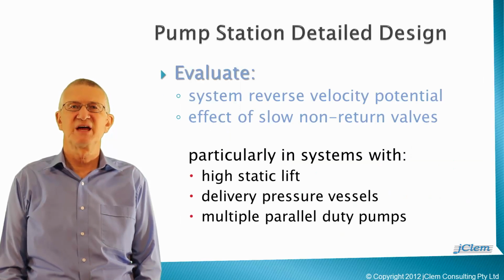Key messages to take away from this lesson are the importance of firstly evaluating the system's potential to generate reverse velocities through the pumps. Secondly, evaluating the consequences of safe operating heads being exceeded or life of the asset being reduced if the non-return valves cannot close at the pace required by the system.